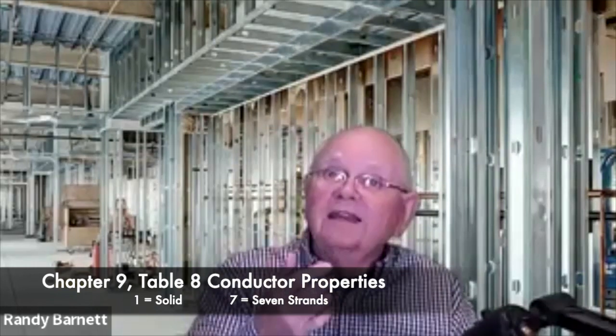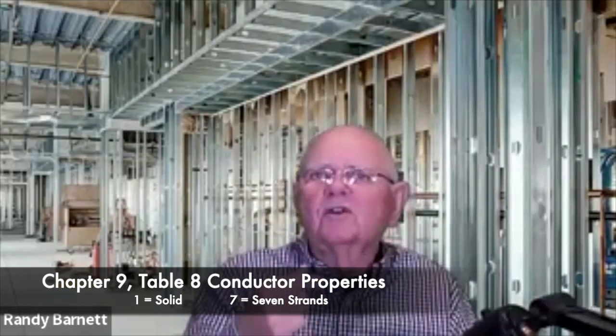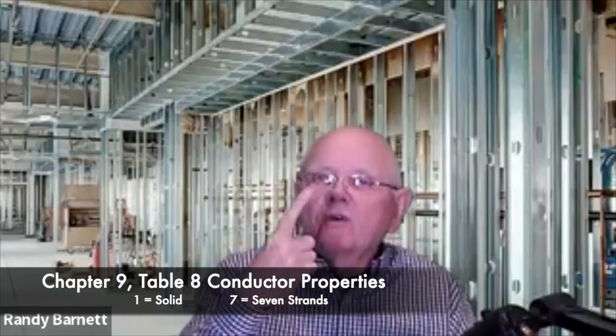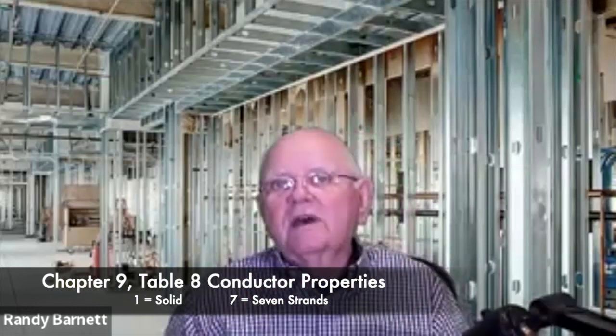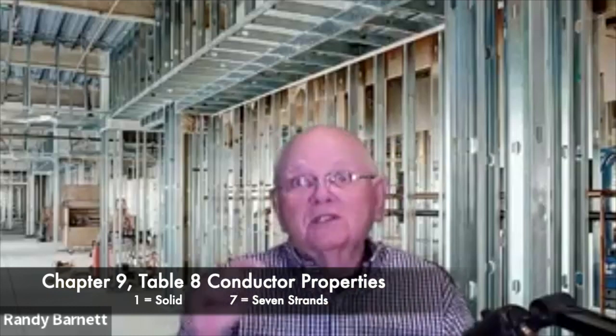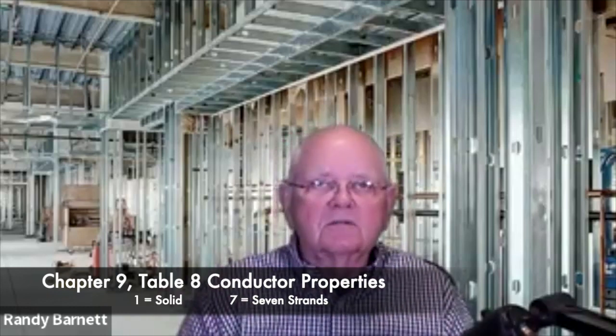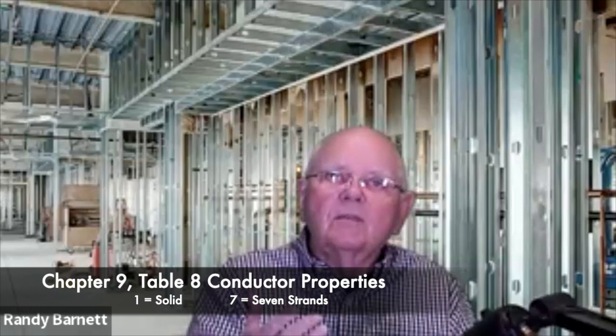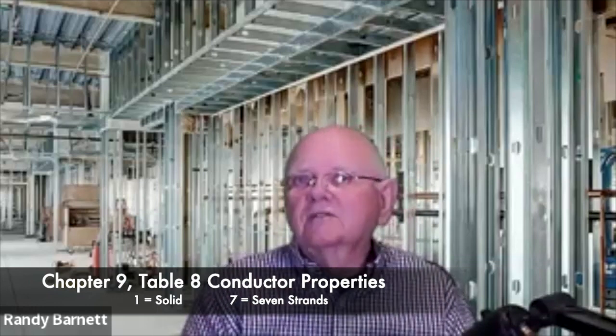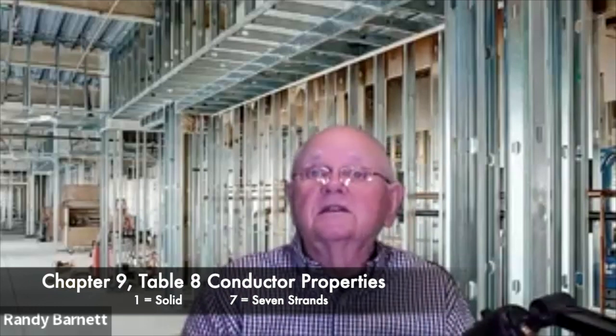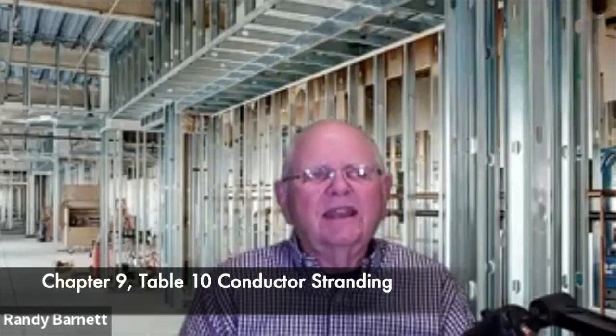And for stranding, it'll list like 1 or 7, or 1 or 19. If it's only one strand, that means they're talking about a solid conductor, so all the dimensions after that are for solid conductors. But if it says 7 or 19, that's the number of strands per that conductor, and that's called B-stranded conductor. So we have B-stranded and C-stranded in the code book, and there's another table in chapter 9, table 10, that talks about conductor stranding.